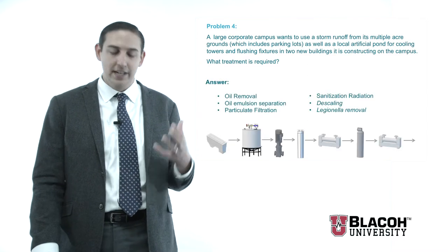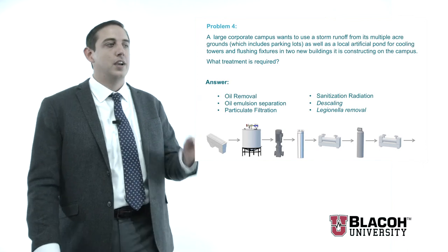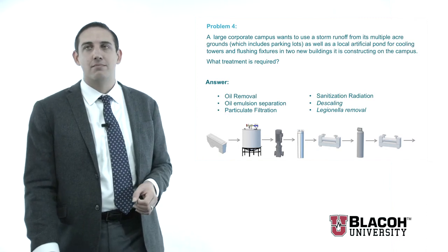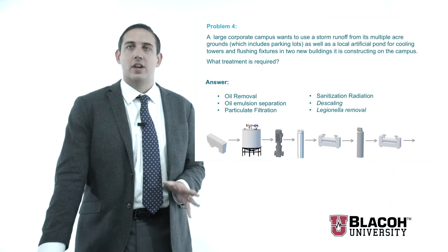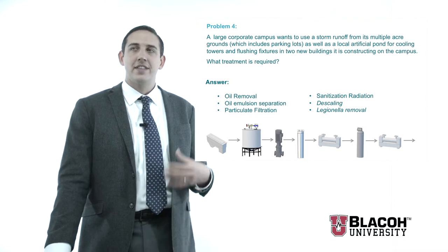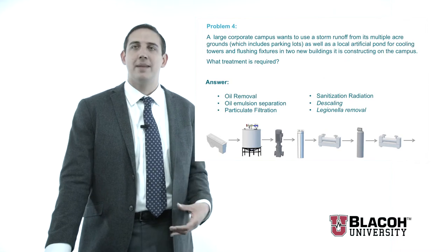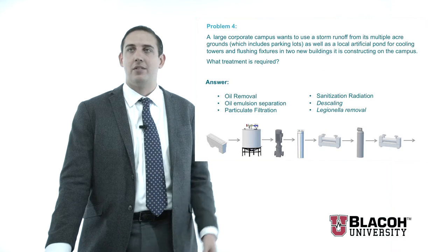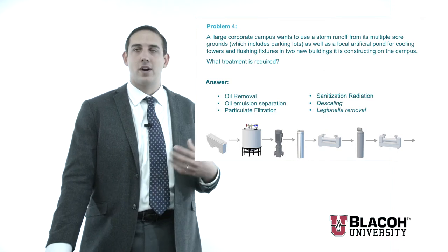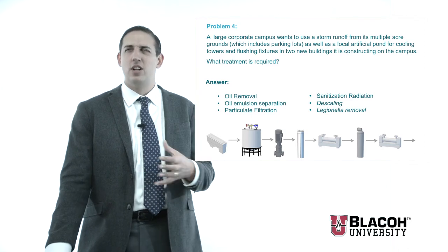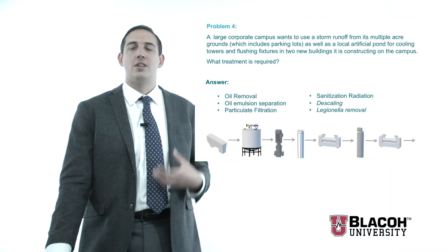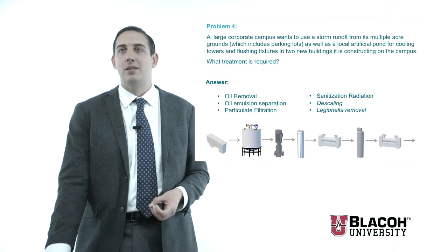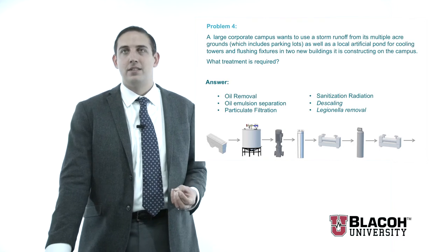Oil and oil emulsion separation is a given any time you're looking at a parking lot or stormwater application. You're going to have particulate removal and sanitization, but you don't quite have as much need in this case for descaling or RO, because you're going through the pond and the ground — which acts like a natural filter — taking a lot of that contamination out at the source. You might need some treatment, but it really wouldn't be much different than pulling well or reservoir water, as long as you don't draw from the very bottom or very top layer of the pond. That centralized middle 70% range is going to be very clean.